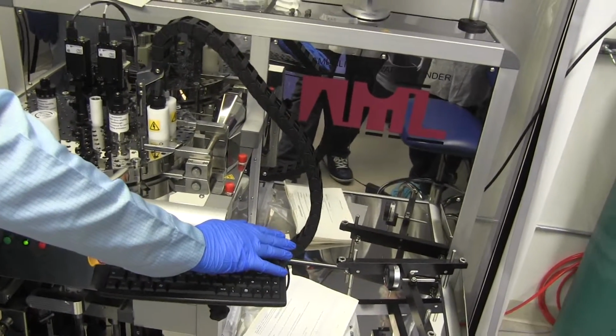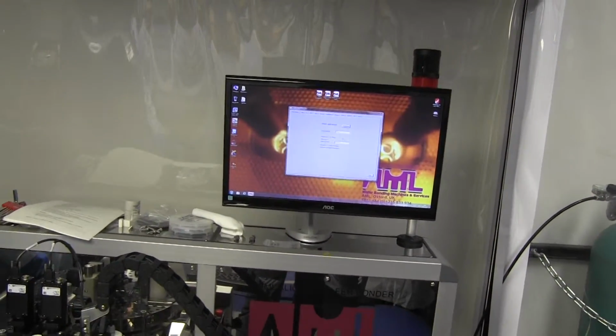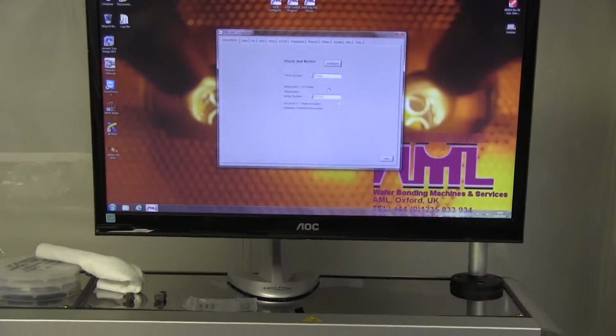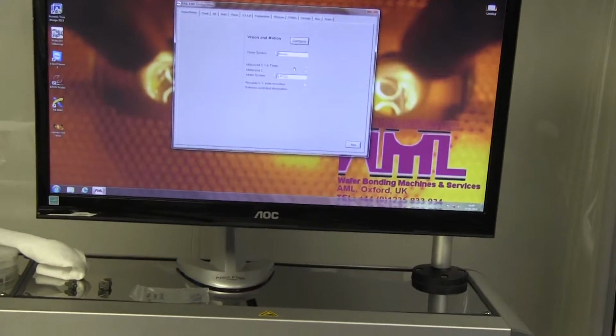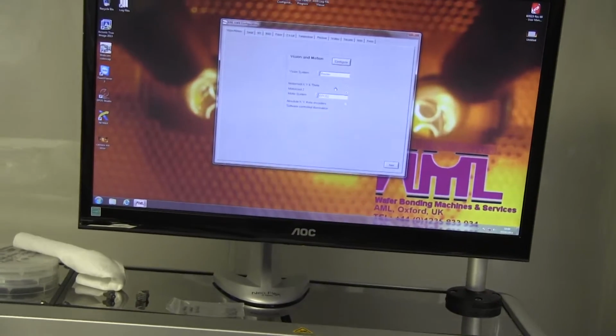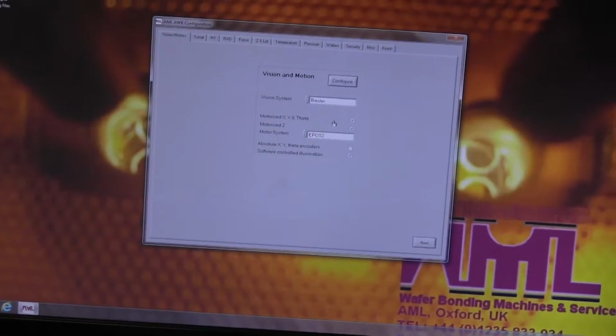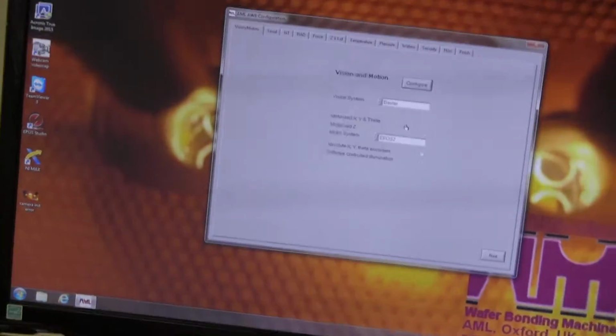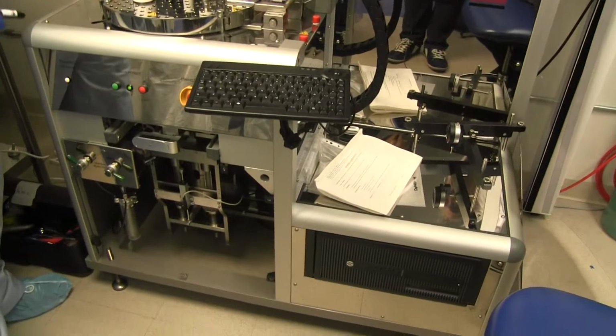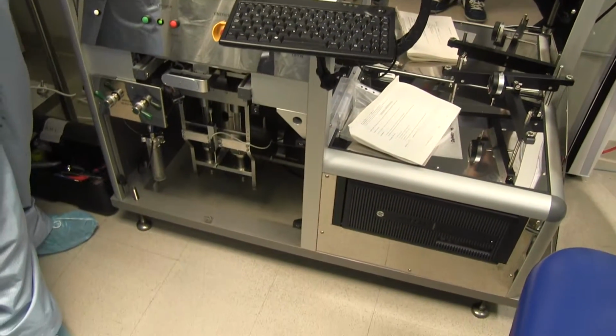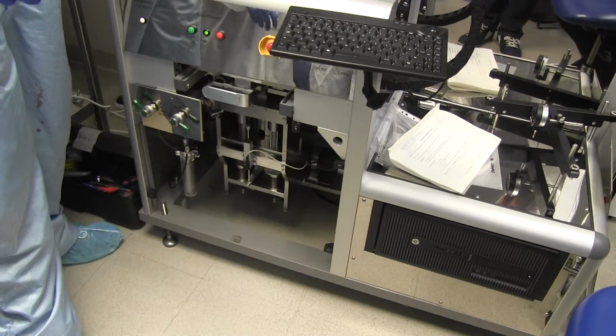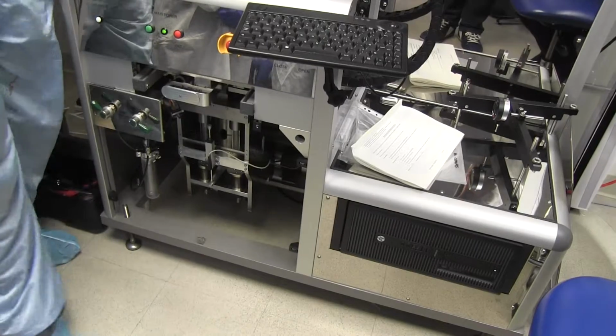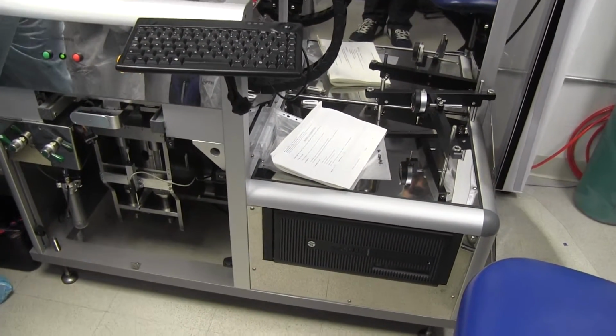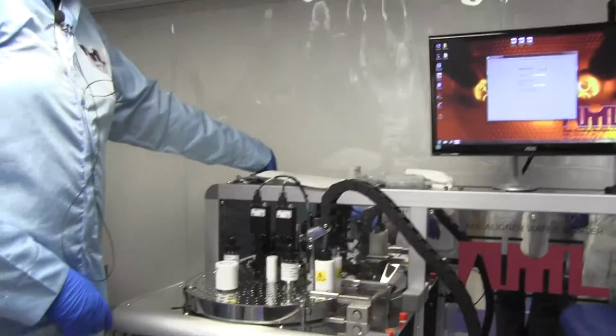We've got some tick boxes here. Motorized X, Y, and theta. All of our systems are equipped with motorized X, Y, and theta controls nowadays. Older machines weren't, so that's tick boxes there for legacy support again. Motorized Z is an option, so at the moment approximately 50% of machines are equipped with it. This particular one is. So I mentioned earlier on there's a motor down there. This one. That drives the Z actuation, the hydraulic system. There is also an option for a manual version which has a big kind of like a submarine hatch wheel that you have to apply force with it manually. Motorized option is a lot better, so you've done well to get that.